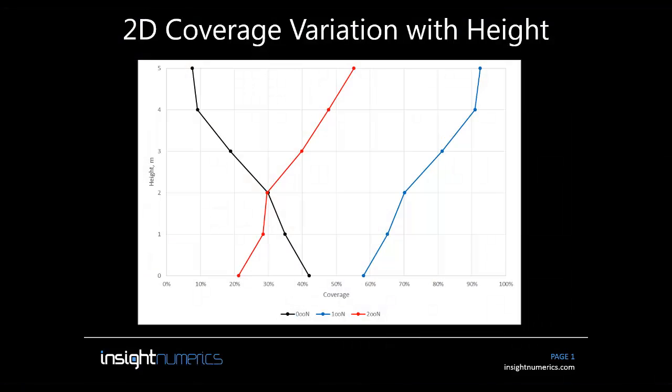I can demonstrate just how much the coverage changes with height using this graph. The X axis shows coverage as calculated by the 2D model, and on the Y axis we have height above ground level. The black line shows zero coverage, the blue line is covered by one or more detectors, and the red line is covered by two or more detectors. You can see that zero coverage is over 40% at ground level but reduces to under 10% at 5 meters height, while coverage of 1 or 2 detectors increases with height. These changes of 30 percentage points or more are very significant. They can mean the difference between complying with performance criteria or not.